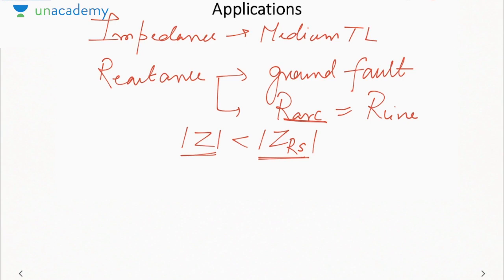And the arc resistance will be approximately equal to line resistance when the line resistance is small. That is only possible if the line is a short transmission line, because resistance is proportional to length: the smaller the length, the lower the resistance. So a reactance relay is used for protection of a short transmission line, where the arc resistance is approximately equal to line resistance. Is it fine?